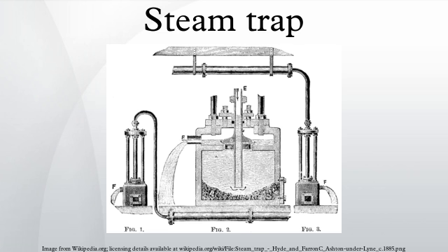Steam traps work best when sized specifically for the application they are used on. Generally it is better to oversize, as they will still discharge condensate when present and close or obstruct the live steam. However, an oversized steam trap may wear quickly, waste energy, and if drastically oversized can cause process issues.